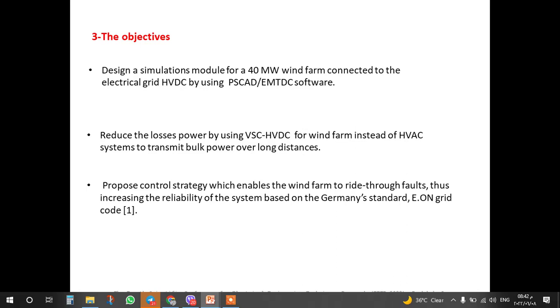Reduce the power losses by using voltage source converter high voltage DC for the wind farm instead of a high voltage AC system to transmit bulk power over long distances. Propose a control strategy which enables the wind farm to ride through faults, thus increasing the reliability of the system based on Germany's E.ON grid code.